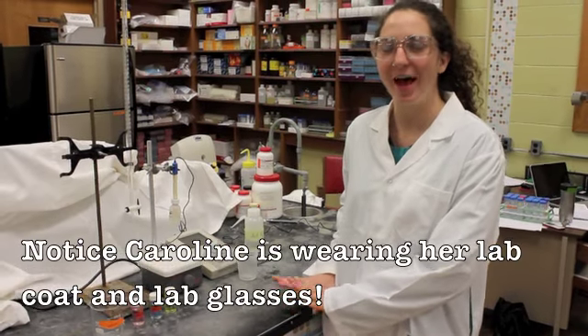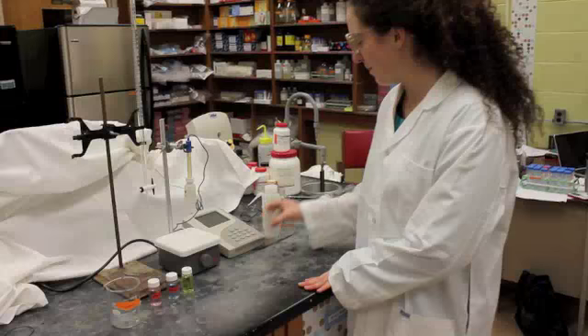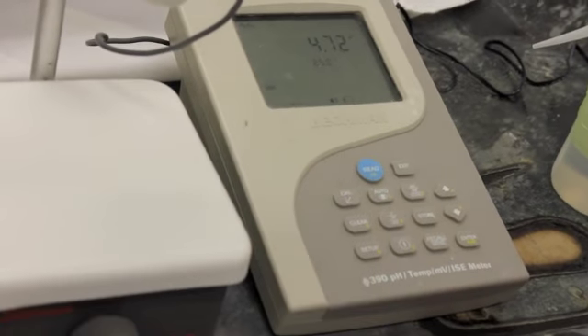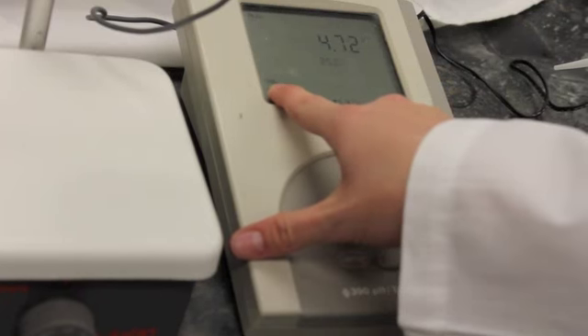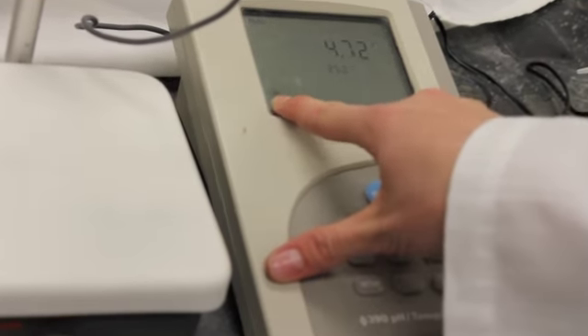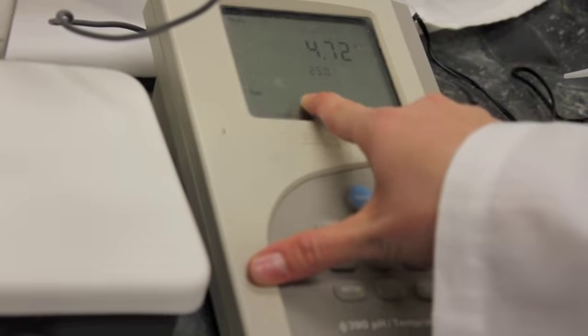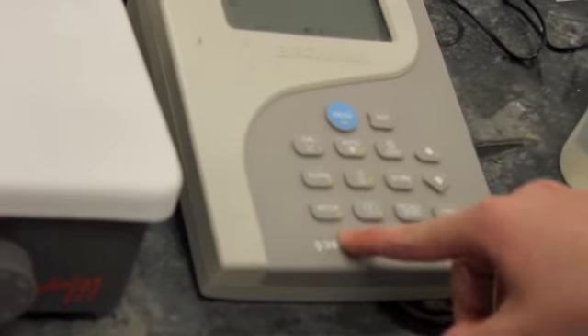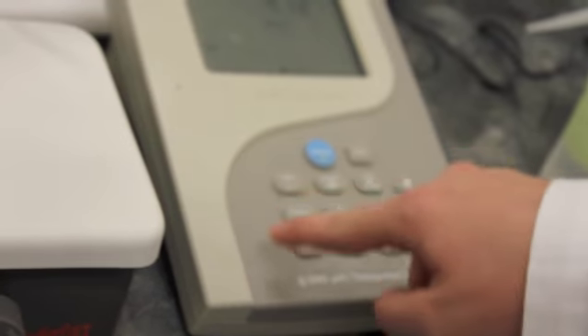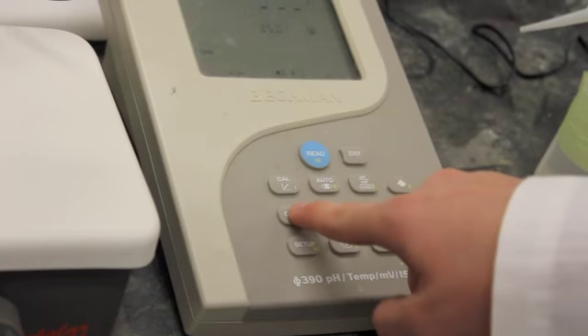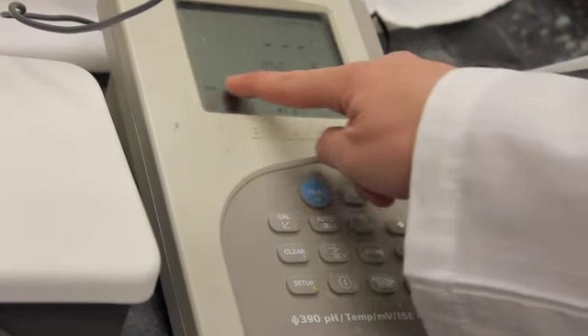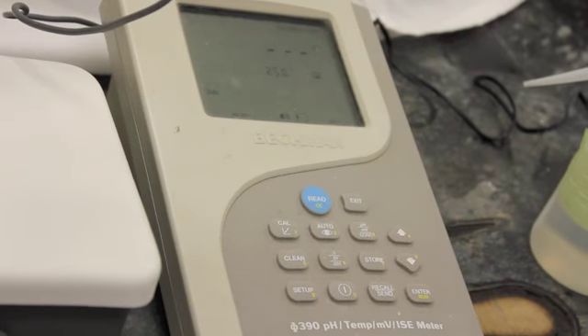First, we're going to show you how to calibrate your pH meter. You begin by turning it on by holding down the on button. In this situation, you see here that the standards have already been cleared. But in the case that it says calibrated, you need to erase the calibration. So you would, if that was the case, press cal and then clear twice to clear the remaining standards, and then you're ready to calibrate.